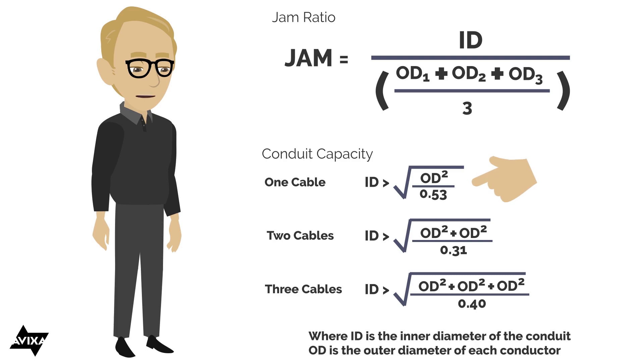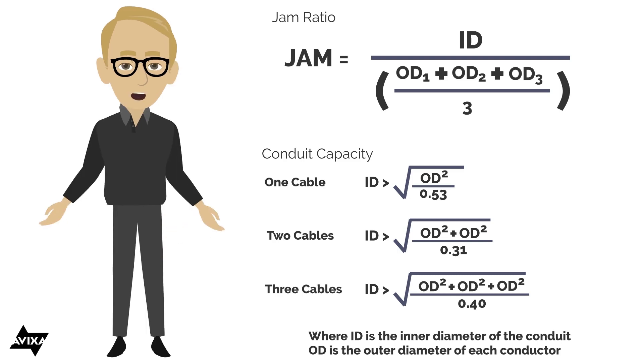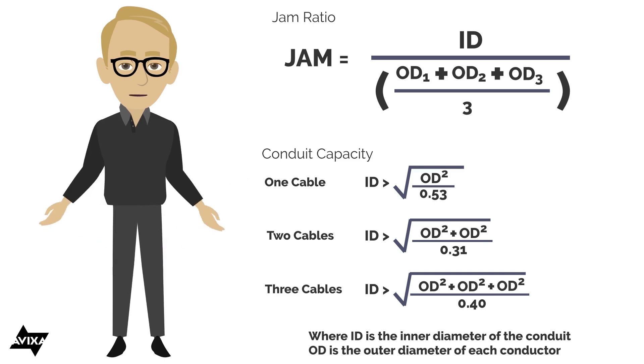On the math sheet you'll see conduit capacity, and you'll see differences if I'm installing just one cable, two cables, or three or more cables. One cable allows up to 53% fill — this could be a single cable or a multi-pair under a single jacket. Two cables allows 31% fill, and three or more allows 40% fill. Your local regulations may vary slightly, but you'll see numbers in that neighborhood.